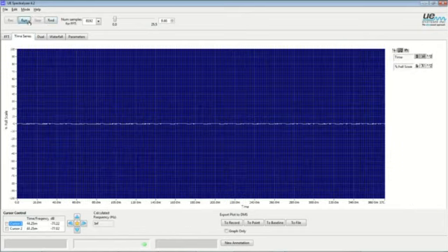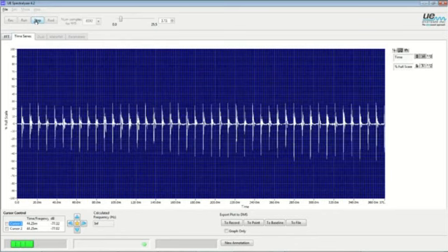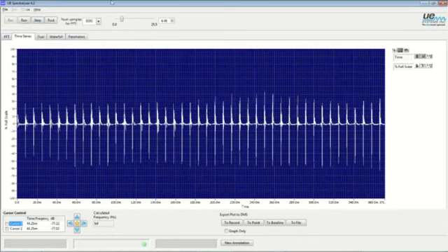In the time analyzer, we can see consistency. So it's a predictable event. On a 60 hertz system with the electromagnetic hum, if you want to characterize it as that, the timing is very consistent on a 16 millisecond time base, and that's illustrated by uniform spacing right here and pretty uniform amplitudes.